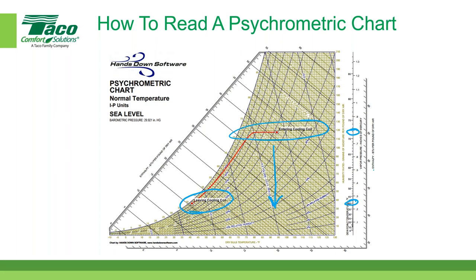Now, this is what John was getting at in terms of the enthalpy. I'm just going to roughly estimate where the enthalpy is. I have it more accurately in the next slide, but I'm going to estimate it here. I think it's around 40, about 42, no, maybe 41, 41 and a half. That looks pretty good. Yeah, there it is. You're talking at the entering coil? Yep. And then it's going to leave here. Again, this is just an estimate. I have a more accurate number in a moment. So it's going to leave there at almost 16.